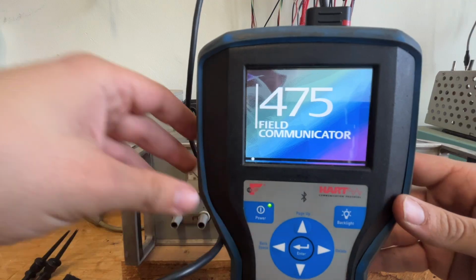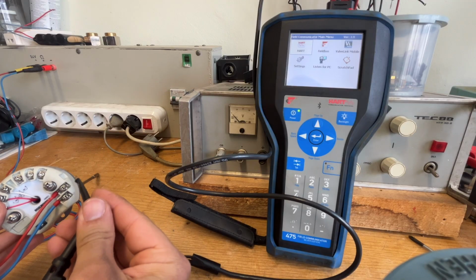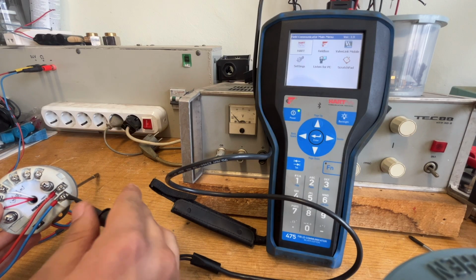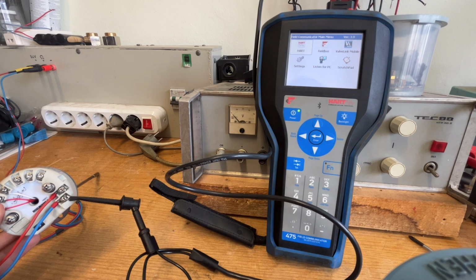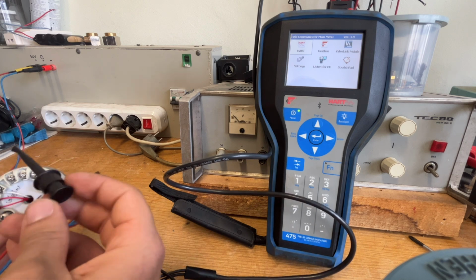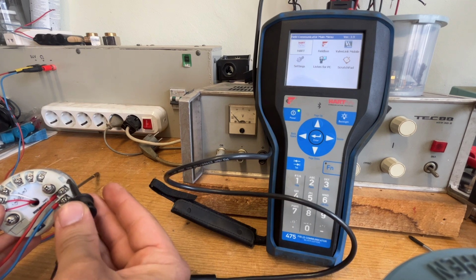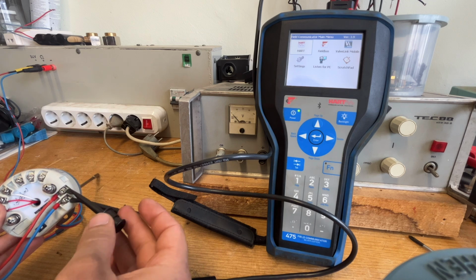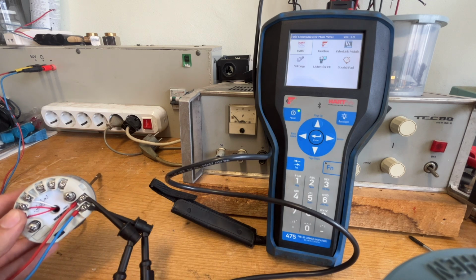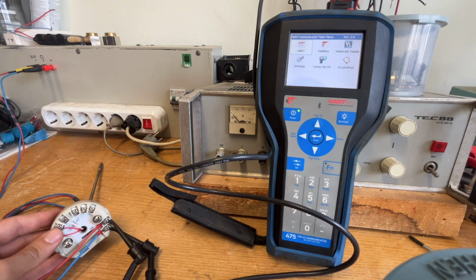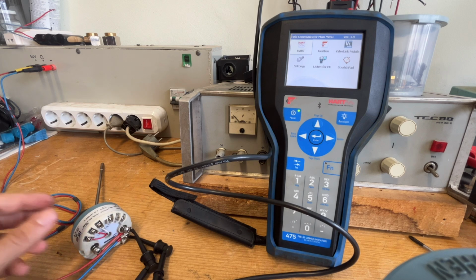The HART communicator needs to be connected across the plus and minus terminals of the transmitter. With the communicator connected, we can now access the transmitter settings and configure it as needed. And that's how you connect a 3-wire RTD to a temperature transmitter. From here, you can configure the transmitter and set it up for your application.